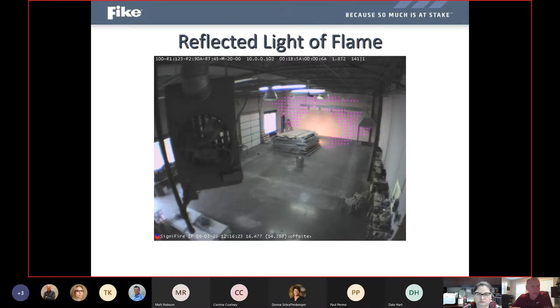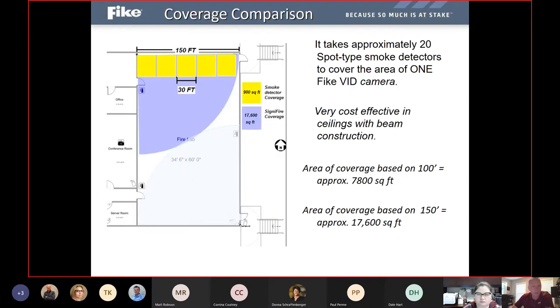And because it is all video-based, this would come right up on a computer monitor somewhere that's running the software. It can also be programmed to send emails to a programmed list of recipients. The email might be a picture or a screenshot of exactly what put the camera into alarm, to show folks, hey, camera number six went into alarm because we see a reflected firelight. If it showed you a short clip of this video or even just a picture of what it's seeing, we would be able to recognize right away that, yes, something is happening that we need to respond to. So very intelligent, intuitive, and flexible to be able to use video camera type systems to detect fire.